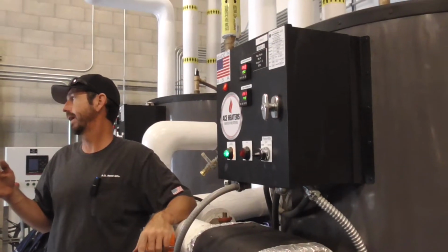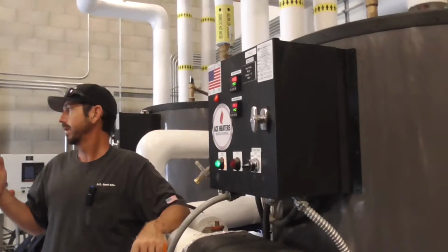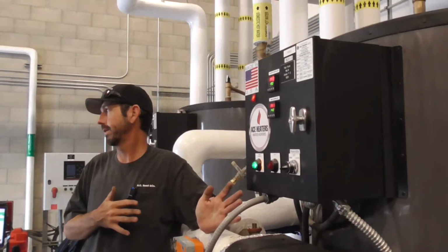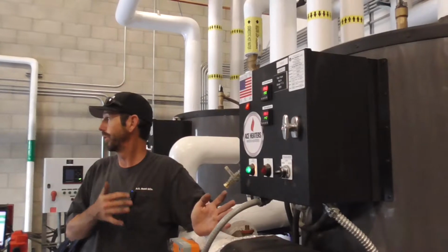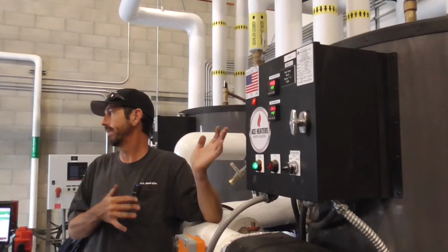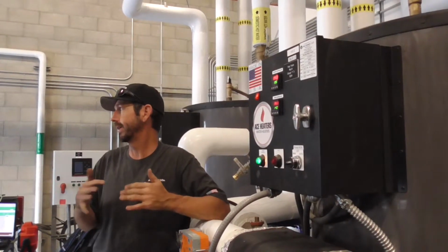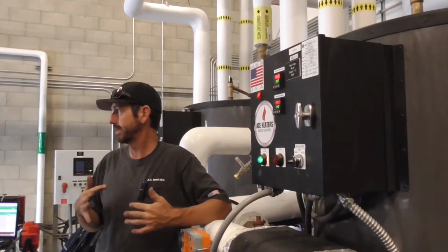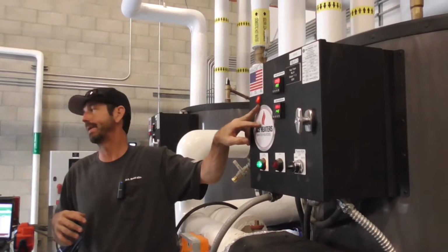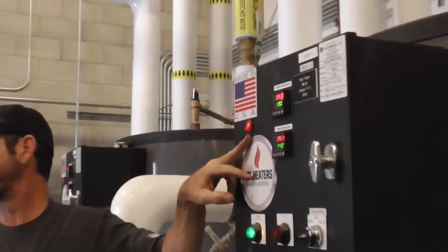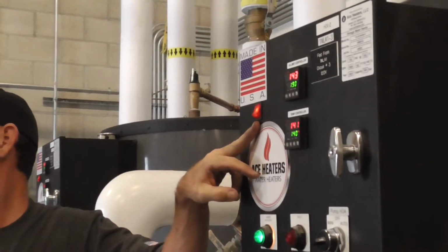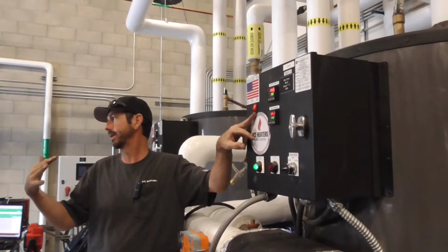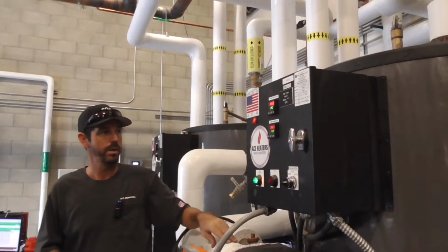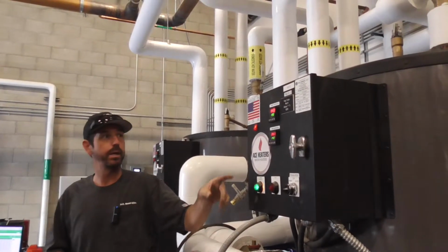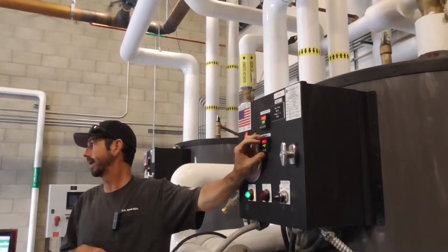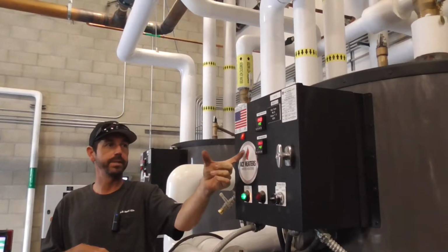It does have an adjusting PID loop. So if it did sit for a long time with no hot water to it, if you're servicing it, you left power onto it, the PID loop is learning that it's not working, and it will make adjustments. So I would just recommend switching off power and cycling power to the unit, and it'll re-establish and it'll start relearning the PID loop. Okay? The controller's behind here. So it's like its body itself.